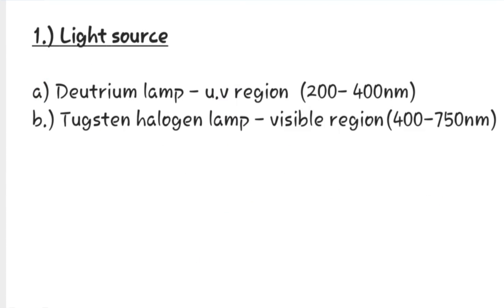The basic component is the light source. Two light sources are most widely used. First is the deuterium lamp. It is used if we need radiations of UV region, i.e., from 200 to 400 nanometers.